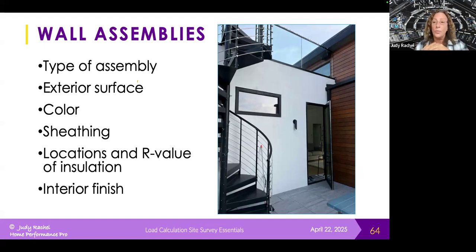Is there sheathing? Older homes typically don't have sheathing; newer homes mostly do. With existing construction we kind of have to guess which walls might have sheathing. On a plan set we can usually see the whole sheathing schedule and put that in appropriately throughout the house. We also need to guess whether it's 3/8 inch wood, 1/2 inch, or 5/8 inch. For new construction that's often not called out on the plan, so we need to ask the architect or contractor what will be used to get the R value correct for the sheathing thickness.